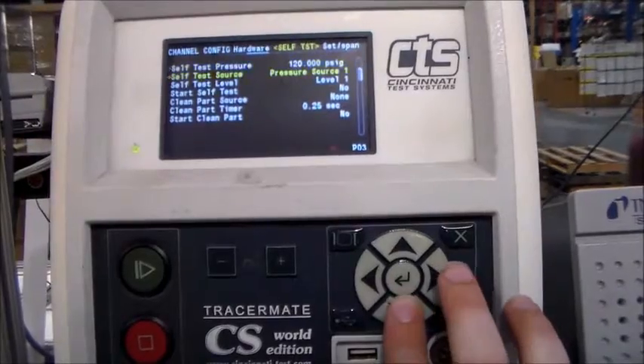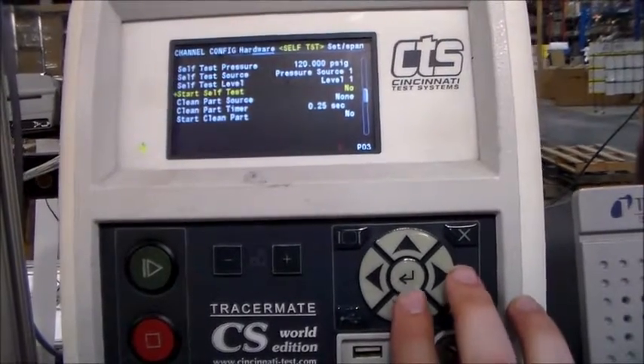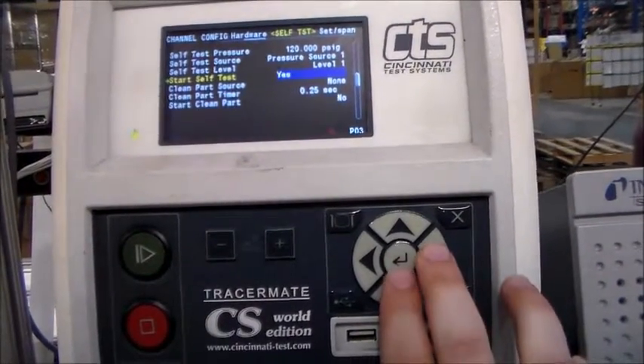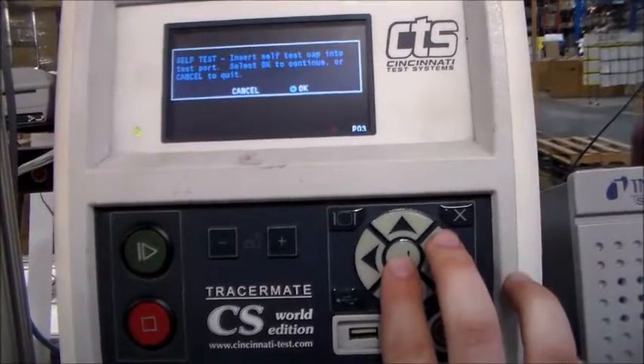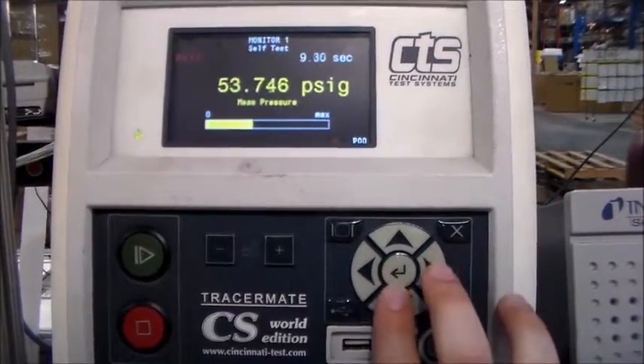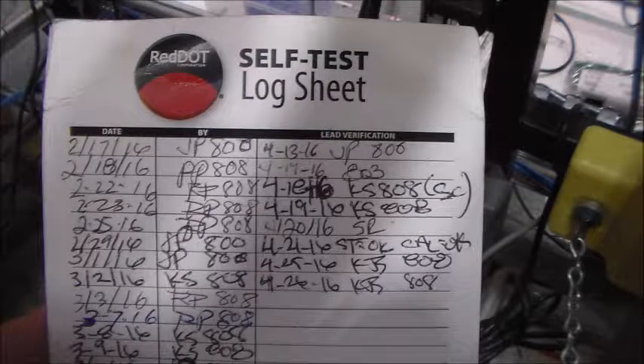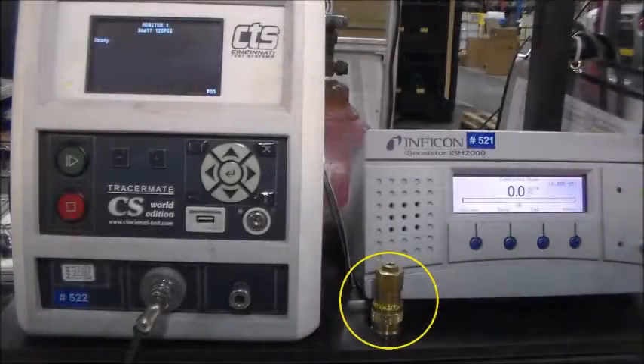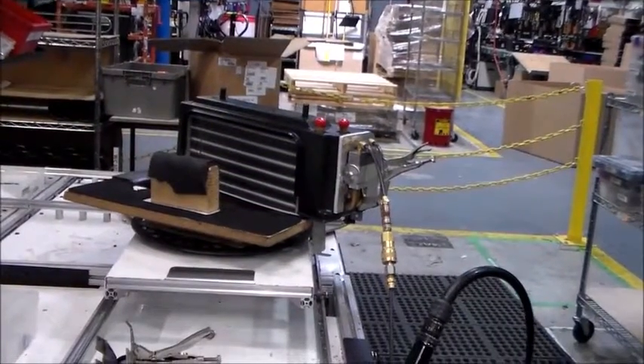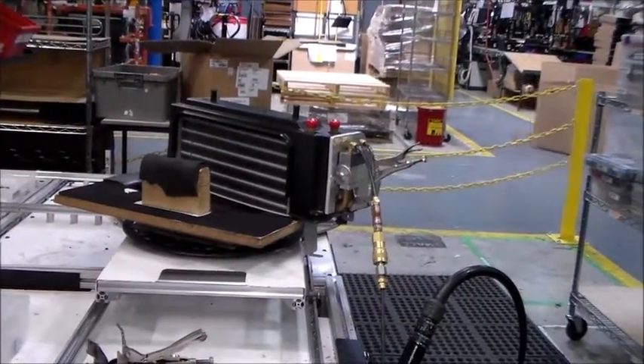Scroll down and change the input on the Start Self-Test line to Yes and press Enter. Double-check the self-test plug is inserted, then press Enter again or Start. If the test is a success, replace the self-test hose with the original testing hose and record the self-test on the log sheet kept with the machine. If the test is a failure, verify your connections and pressures are correct, then retest. If the self-test fails again, ask your supervisor or lead to assist you.